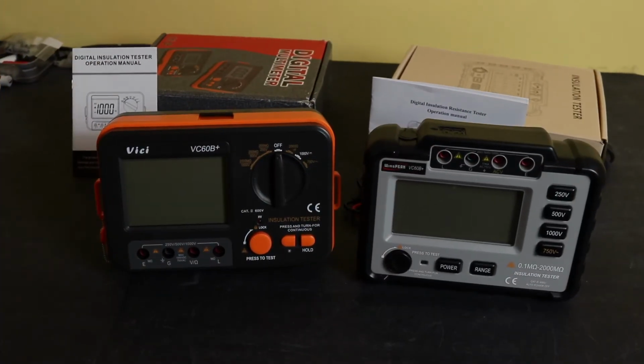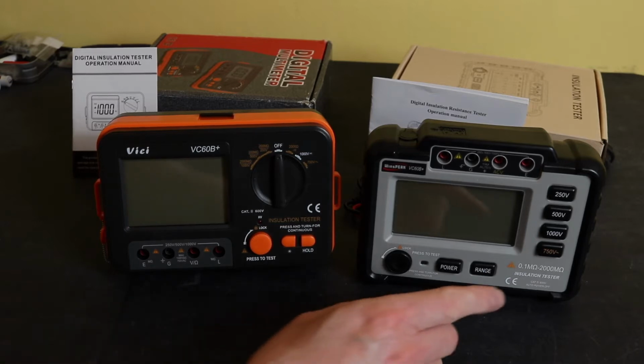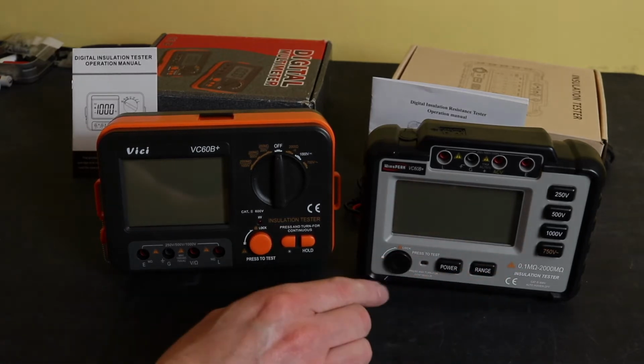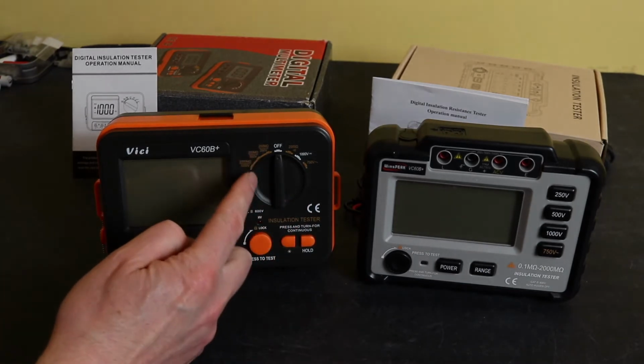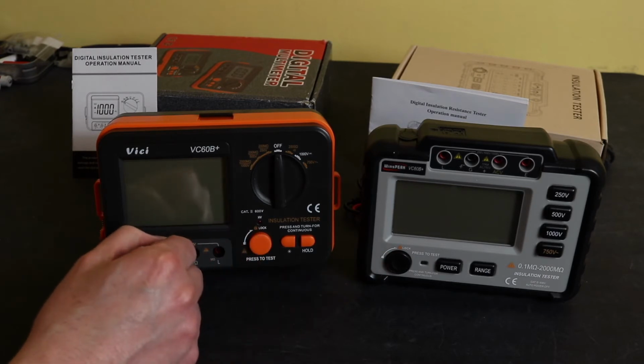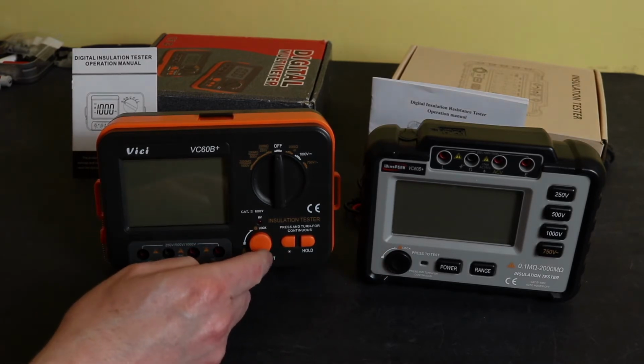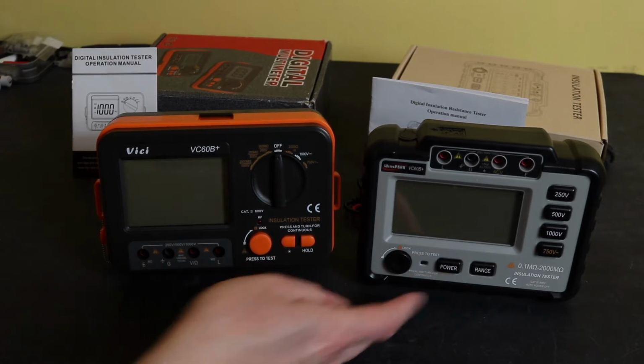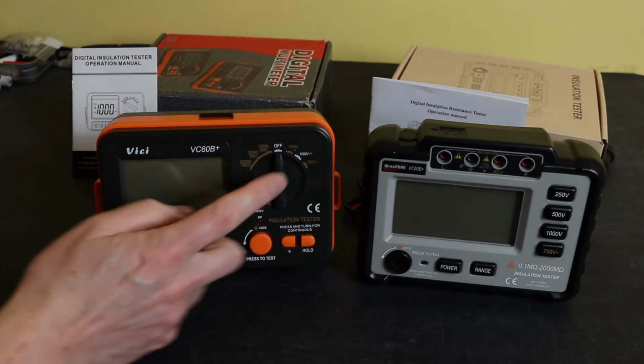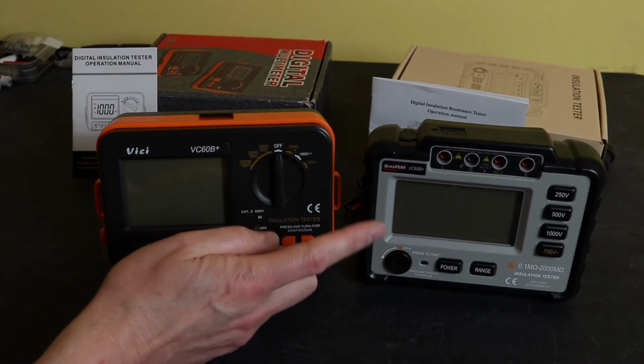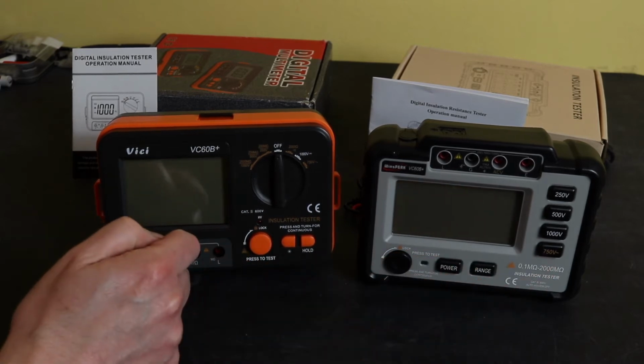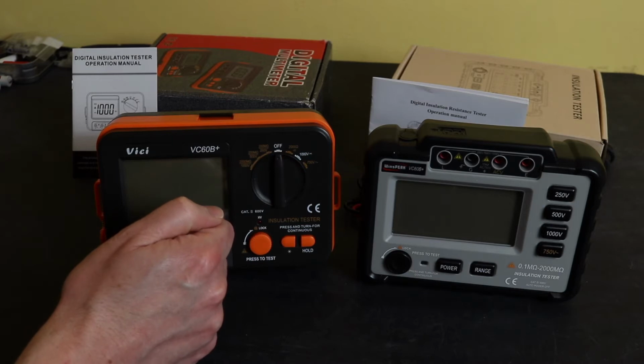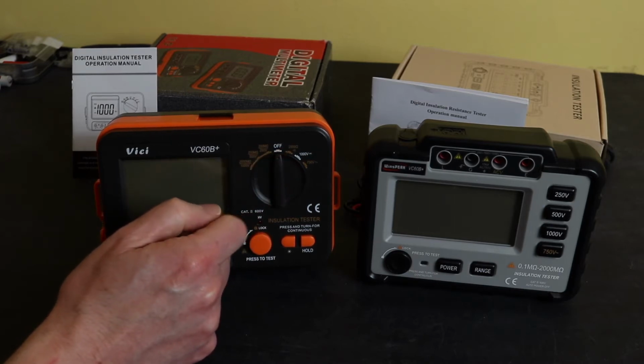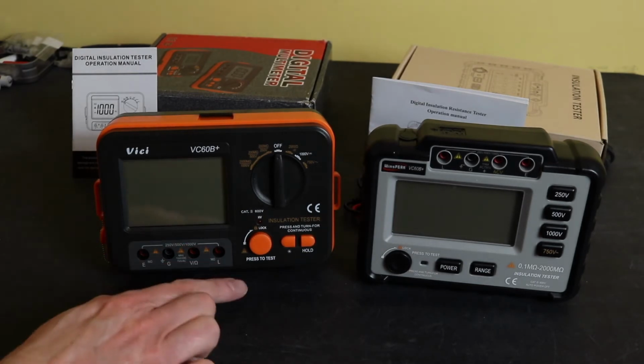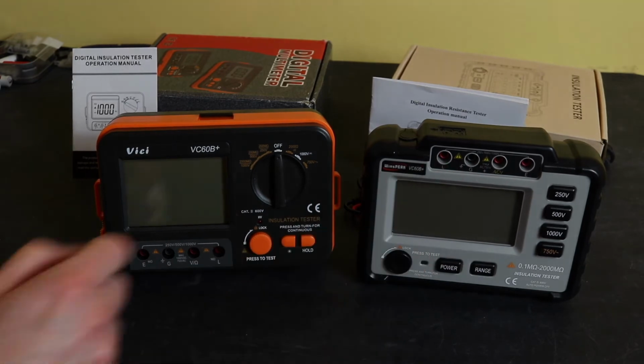So with regard to functionality, the WinsPEAK unit there is the closest to the Victor Instruments unit in both the selection buttons and the operation of the unit. The Vici unit here has a rotary switch as opposed to the selection buttons, and it has a separate light and hold unit. There's no data hold unit on the WinsPEAK unit. This unit also has DC and AC voltage measurement, whereas the WinsPEAK and the Victor Instruments only has AC voltage measurement. You also have an ohms and continuity, 2 mega ohms and continuity range function on the Vici 60B as well. Both instruments have 4 input jacks here.